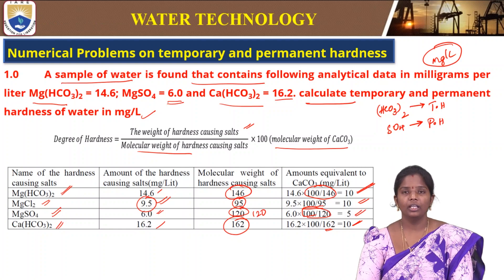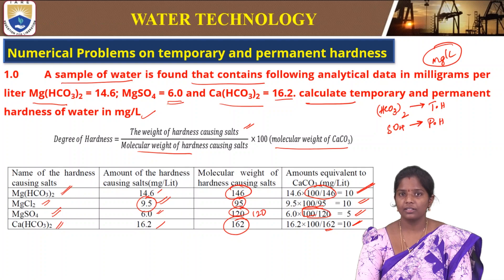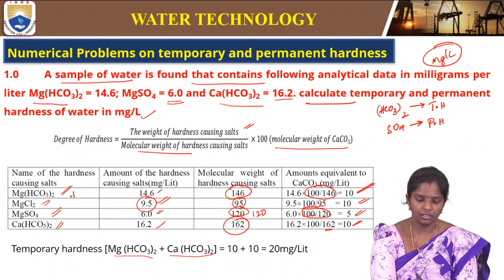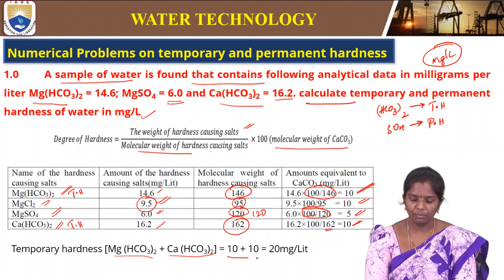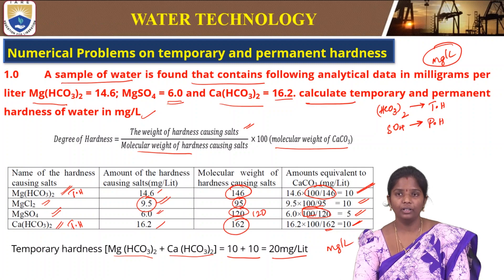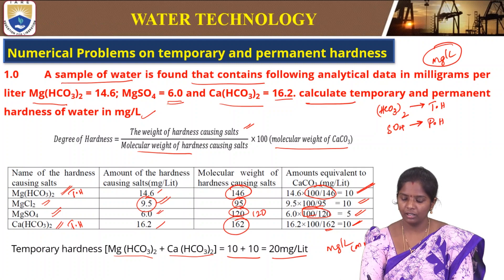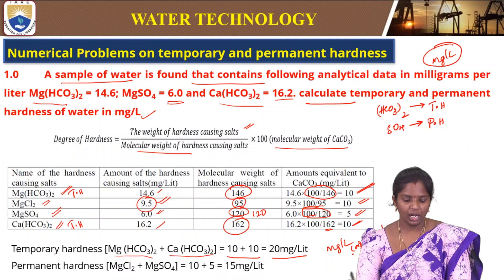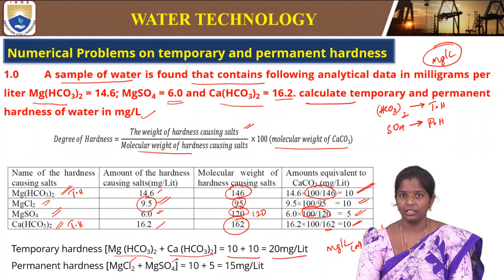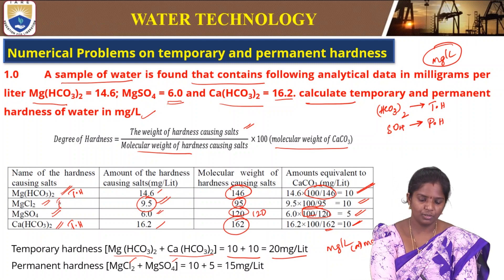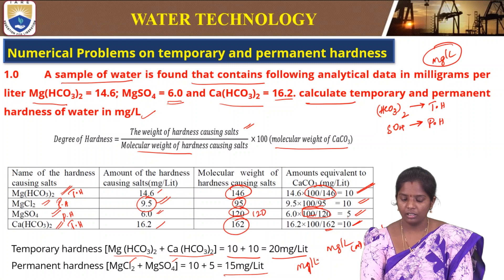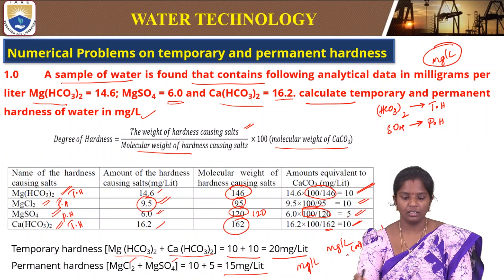Now we calculate temporary and permanent hardness. Bicarbonate salts cause temporary hardness — magnesium bicarbonate and calcium bicarbonate — so 10 + 10 = 20 mg/L temporary hardness. Permanent hardness is due to chlorides and sulphates, so 10 + 5 = 15 mg/L permanent hardness. These are the hardness concentrations present in that particular water sample.